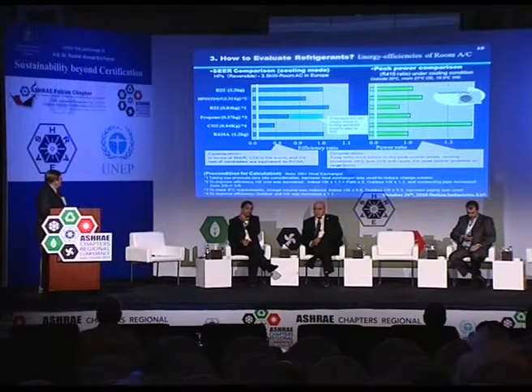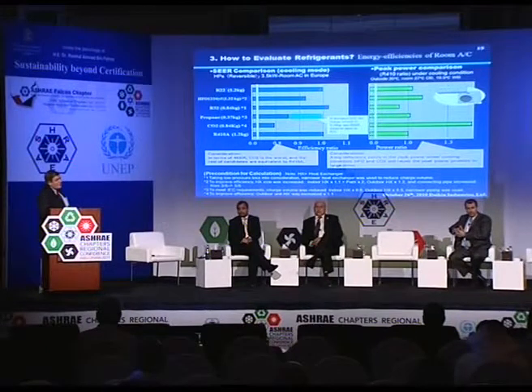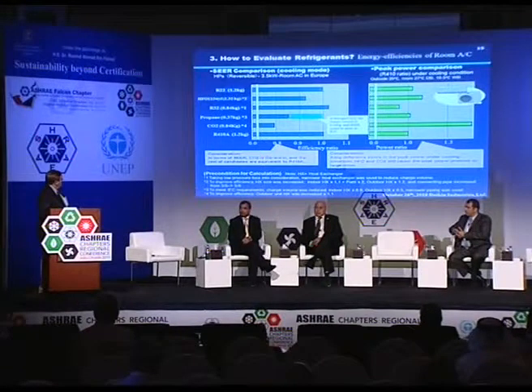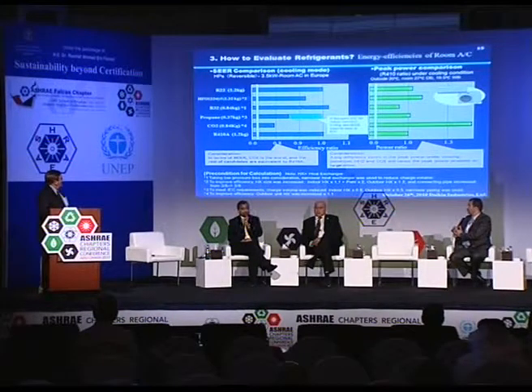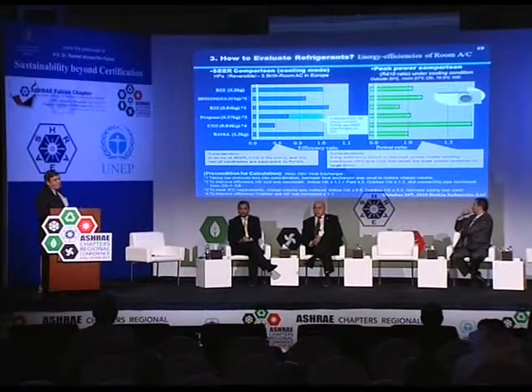This is a simple slide done for a 3.5 kW room unit in Europe. We looked at two comparisons: seasonal energy efficiency and peak power. R22, the baseline, is about here, and the further right you go on this chart, the better off you are. It looks like R32 is one of the substitutes for R22, and it's actually more efficient, so in that category it looks very good. 410A is about the same as R22, but the one that really stands out as problematic is CO2, so it would not be a choice if you're looking for seasonal energy efficiency.